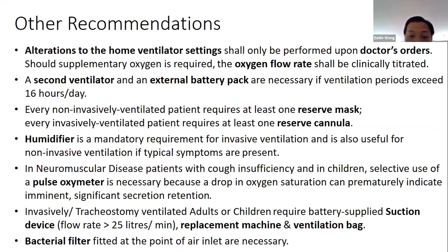Invasively or tracheostomy ventilated patients, adult or children, require a battery-supplied suction pump. So you need to source a suction pump. The recommended flow rate is more than 25 liters per minute. And if you can afford it, get a second suction pump unit, or at least learn how to use a ventilation bag in case the patient needs to be readmitted to hospital during an emergency. At the end, I will show you a YouTube video link so you can watch it after this section. A bacterial filter is fitted at the point where I already mentioned the bacterial filter.